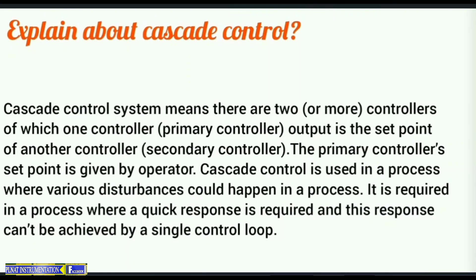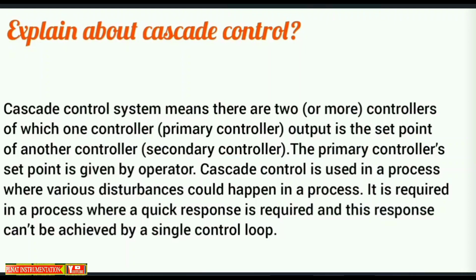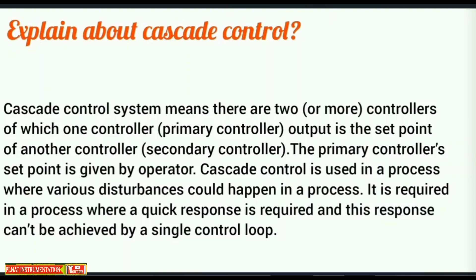Explain about Cascade control. Cascade control system means there are two or more controllers, of which one controller's (primary controller) output is the set point of another controller (secondary controller). The primary controller set point is given by the operator. Cascade control is used in processes where various disturbances could occur and a quick response is required that cannot be achieved by a single control loop.